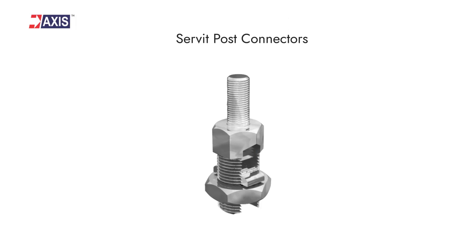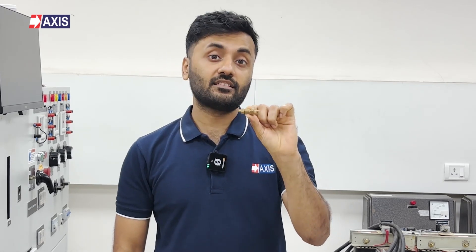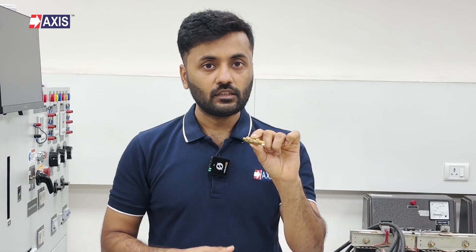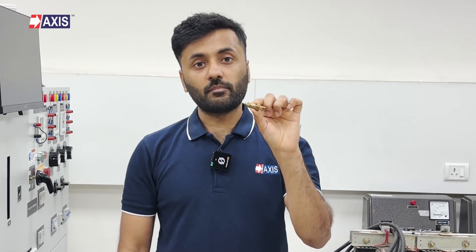Next, let's look at Servit Post connectors. Can you see this threaded part which is sticking out? It connects other components like busbars as needed. Without this threaded part, it would have been just like a split-bore connector. Servit Post connectors are designed to make copper-to-copper connections, such as connecting the conductor to the busbar in a transformer. Other applications include grounding steel structures and fence posts. We offer various types of Servit Post connectors, including copper, tin-plated, brass, and more.